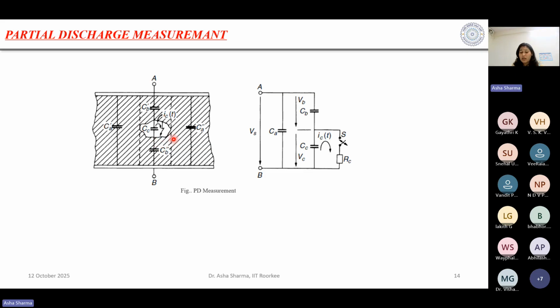But why are we still not able to completely avoid this partial discharge phenomenon? Let's say you think of this transformer. The transformer is huge, and the insulation used in the transformer is again huge, right? The voids or cavities causing partial discharge are very small bubbles. If I am talking about something 100 centimeters, in this case we are just talking about something 1 micrometer, 1 nanometer. So in this huge insulation system, these things are very, very tiny. So again, in the measurement techniques, we are not sure whether these measurements are accurate or not because of the difference in scale. The causes of partial discharge are very tiny, and the complete insulation system is very large. So that's why it is something that we are still figuring out. How can we detect and localize the partial discharge? One thing I can tell you is that we use acoustic sensors for partial discharge detection these days.